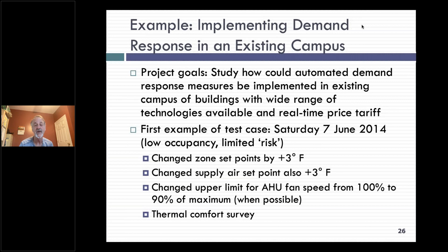We changed the zone supply temperature or zone set point temperatures and the supply temperatures, and put a limit on things like the air handling unit fan speeds. After implementing and testing that, we also did a thermal comfort survey to see if people even noticed it. We did this on part of the campus, within a chilled water distribution network, using two of the main buildings - you can see this in the picture right there on the campus.